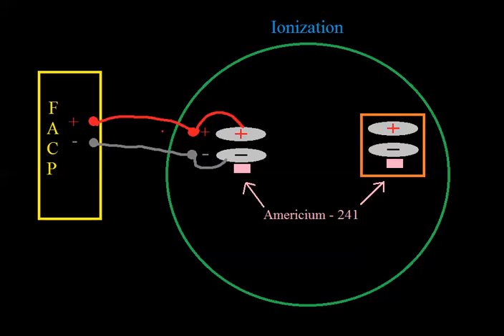Now, you see this thing on the right here—that's what's called the reference chamber. That's in most of these newer ionization detectors. Let's just draw our power over here. This would be on a very small portion of the smoke detector. I'm drawing it spaced out so it's easy to see what's going on. But this reference chamber is sealed. It basically does not allow smoke to get into this chamber. So these two things on the right and the left are identical, except that the one in this orange box does not allow smoke in.